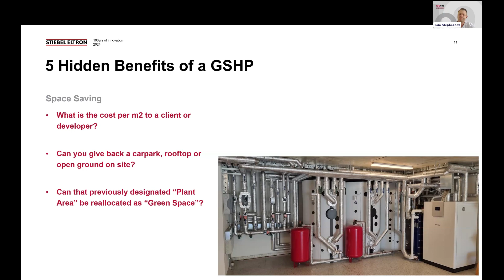The connected load savings is a big one. For electrical connections, we know heat pumps use electricity, and ground source heat pumps will use less. But in consolidating all of those services, because we can heat, cool, do potable hot water, pool heating, any of your thermal activities, bringing all of those connected loads of individual devices onto one greater system provides benefits, not just in the calculation of connected load, but also in the cost incurred by having that excess electrical infrastructure. From that, the system can then be cascaded to build higher capacity or build in redundancy.